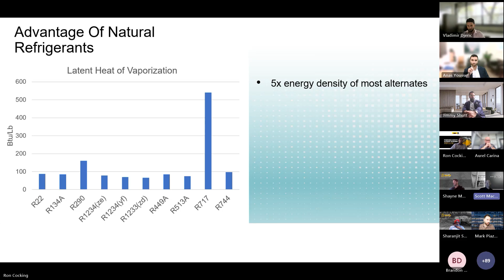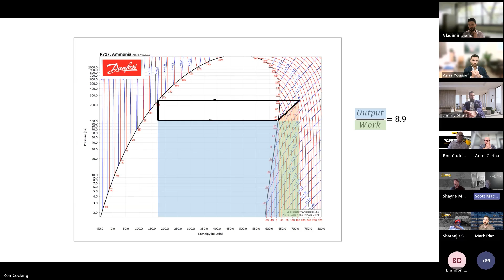When we apply this to a coefficient of performance for an ammonia package, what we've got here is a pressure enthalpy chart. Hopefully some of you are familiar with these. It's an R717 ammonia package at design conditions for a very standard data center application, and it provides a coefficient of performance of 8.9, which is exceptional.